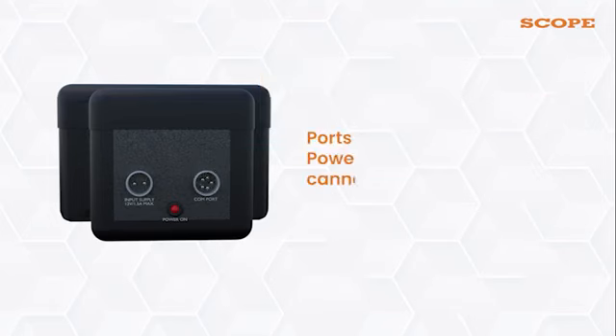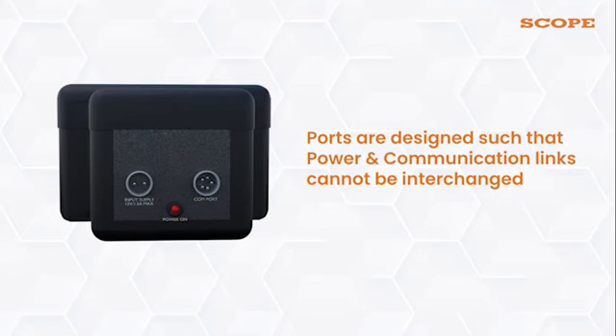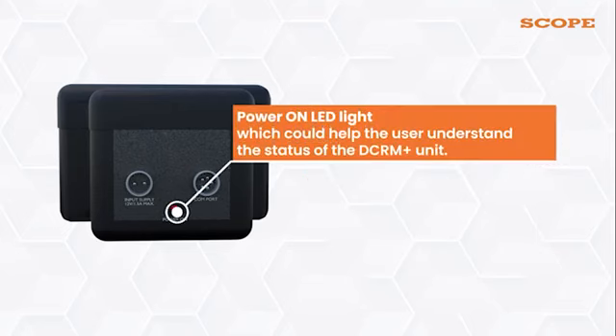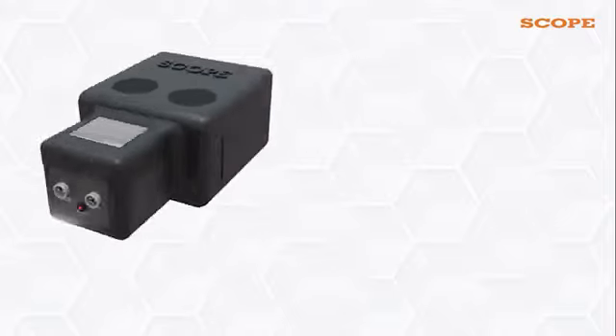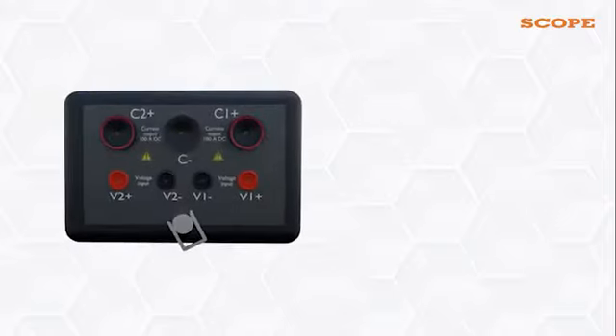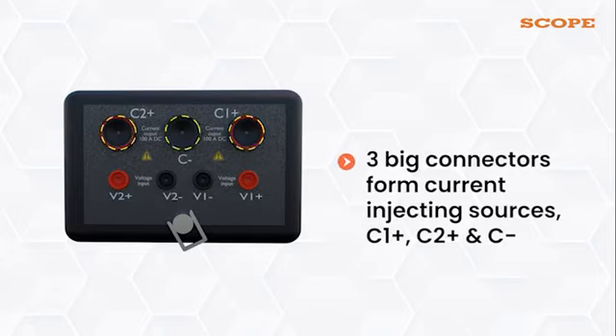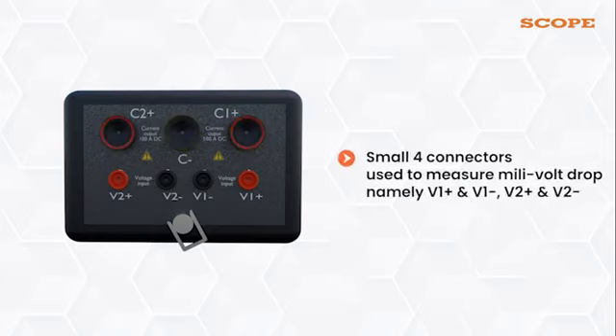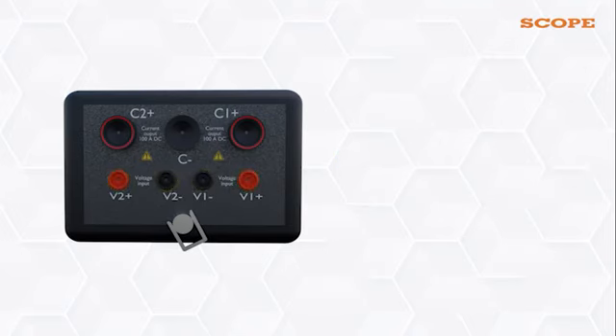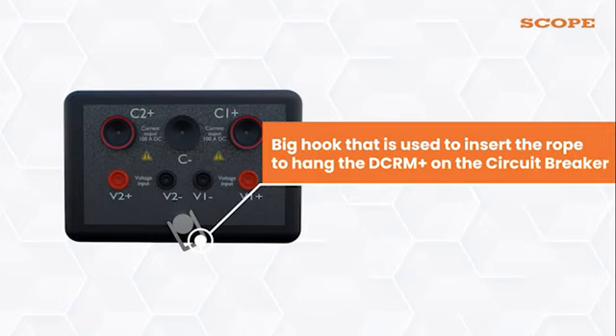Ports are designed such that power and communication links cannot be interchanged. Also, there is a power on LED light, which could help the user to understand the status of the DCRM Plus unit. On the top of this handheld unit has the following connectors. 3 big connectors form current injecting sources, C1+, C2+, and C-, whereas small 4 connectors are used to measure the millivolt drop, namely V1+ and V1-, V2+ and V2-. Also, it has a big hook that is used to insert the rope to hang the DCRM Plus on the circuit breaker.